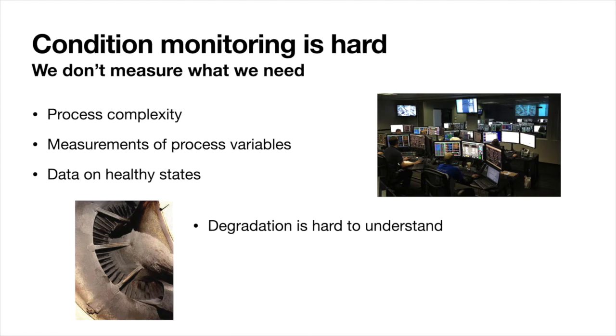Moreover, while we can have a lot of data, because almost every process variable is measured, we mostly have data on healthy states. And faulty states come from degradation, which is really a difficult problem. For example, compressors accumulate dust. Dust makes their efficiency lower. Lowering efficiency, however, is not a monotonous process, because collected dust can fall away from the walls of the machine. In that situation, observing just efficiency won't give us information about the condition of the system.